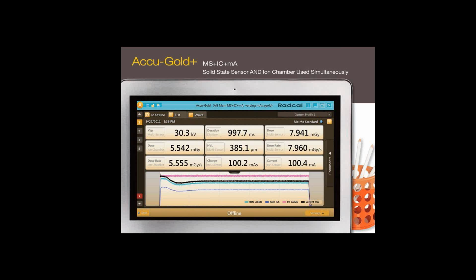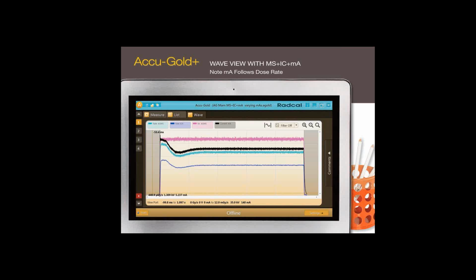This exposure from another session shows the use and display of both a multi-sensor and an ion chamber simultaneously measured. Displayed is the kVp, multi-sensor dose and dose rate, and the ion chamber dose and dose rate. The respective waveforms are also shown in the measurement below. And here is the expanded waveform of the previous exposure for further analysis.